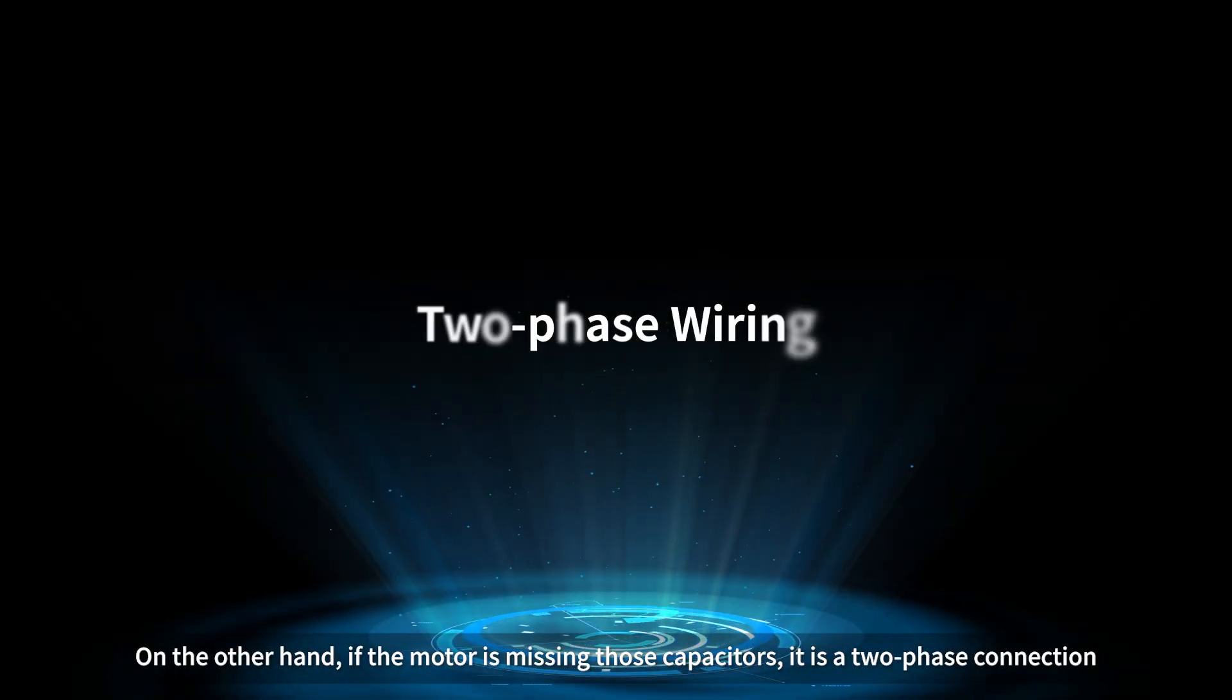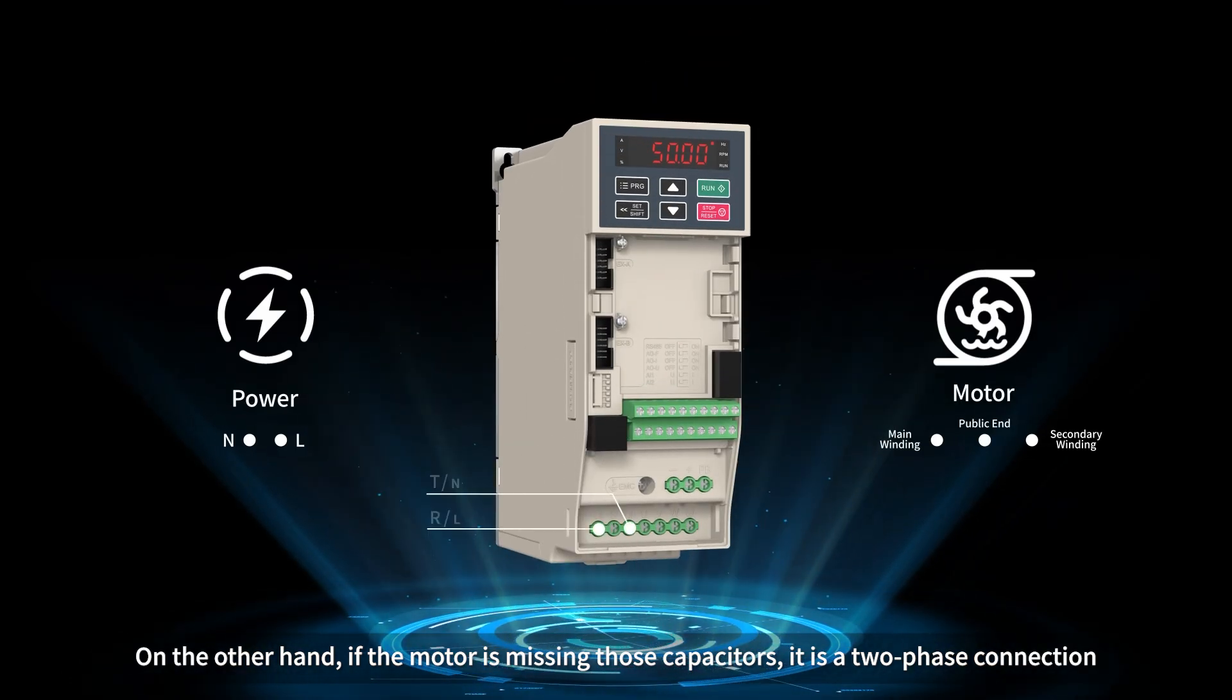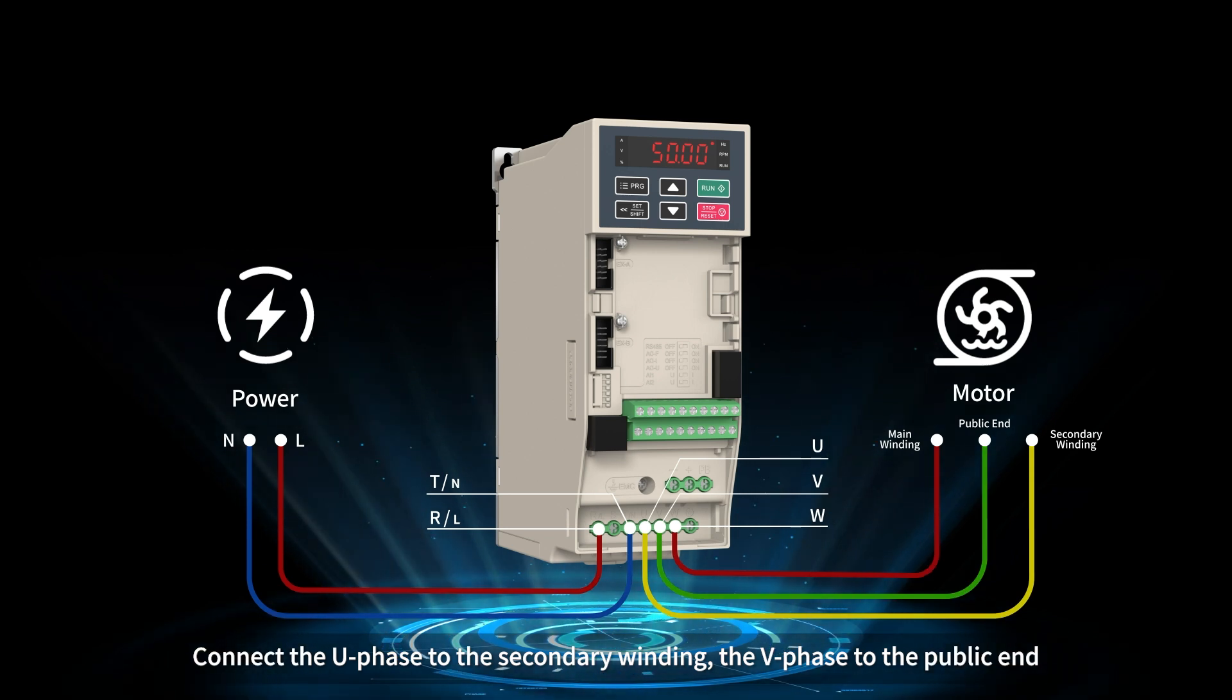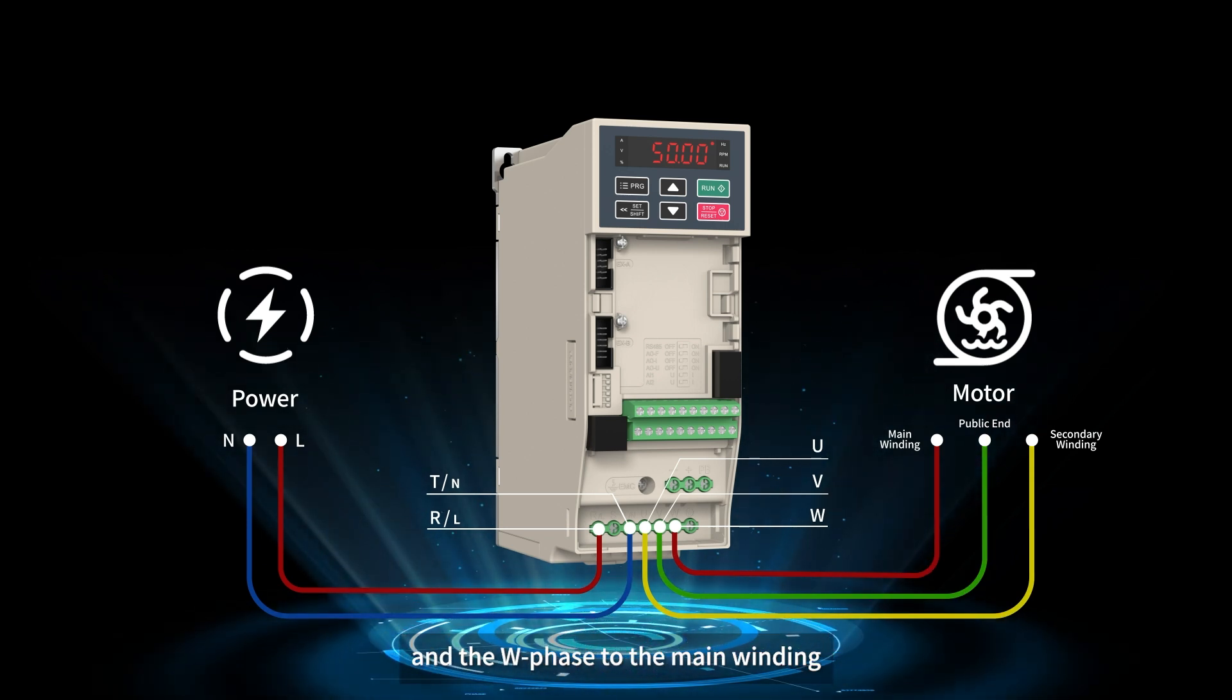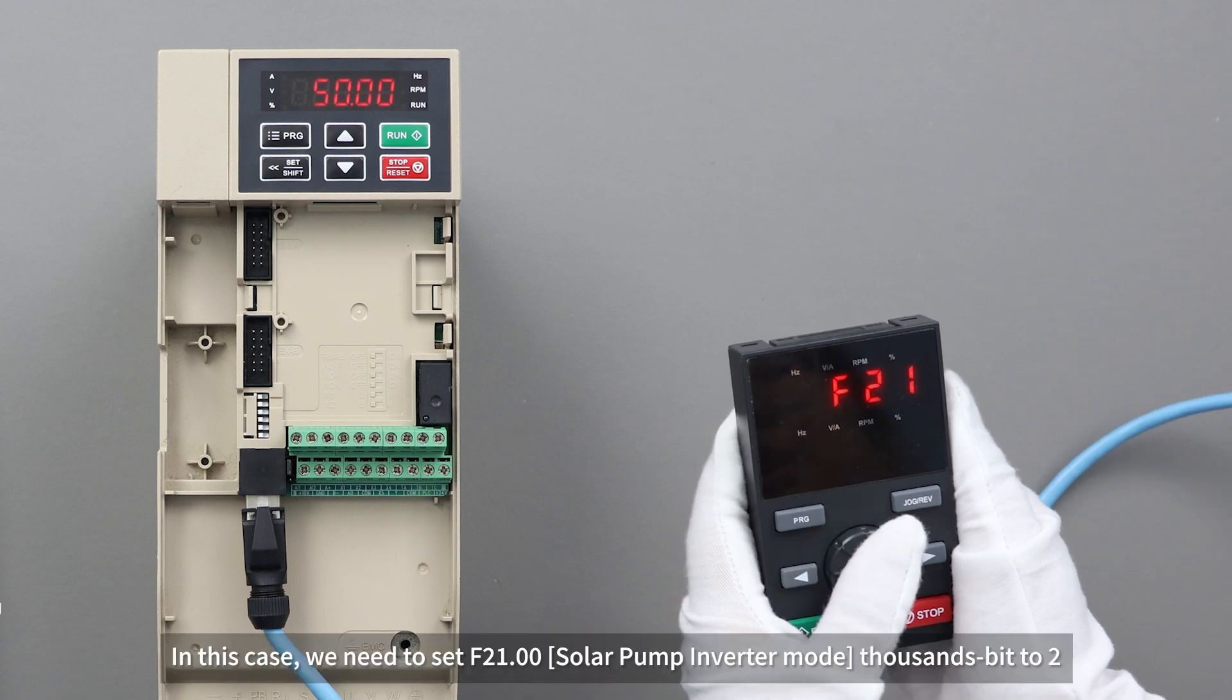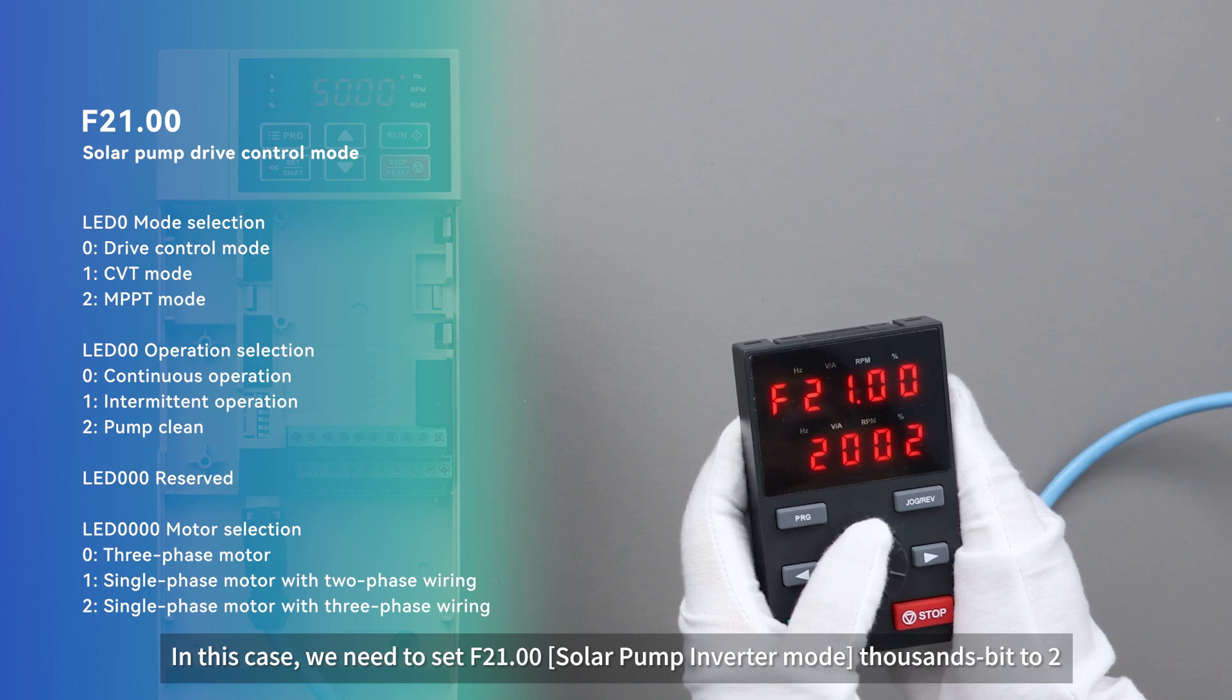On the other hand, if the motor is missing those capacitors, it is a two-phase connection. Connect the U phase to the secondary winding, the V phase to the public end, and the W phase to the main winding. In this case, we need to set F21.00 thousands bit to 2.